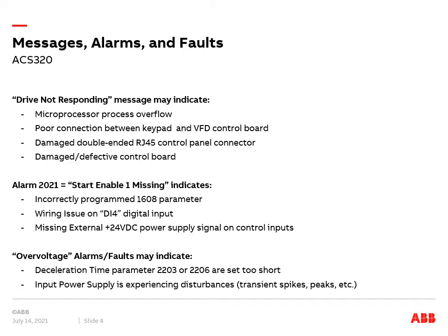This can be the control panel's fault, the control board's fault, or the double-ended RJ45 adapter that connects the two. If field bus communications are connected to the drive and the drive was otherwise operational before the message occurred, then the microprocessor may be impeded by corrupted data.